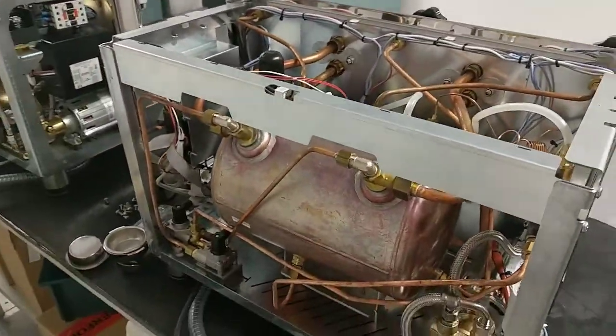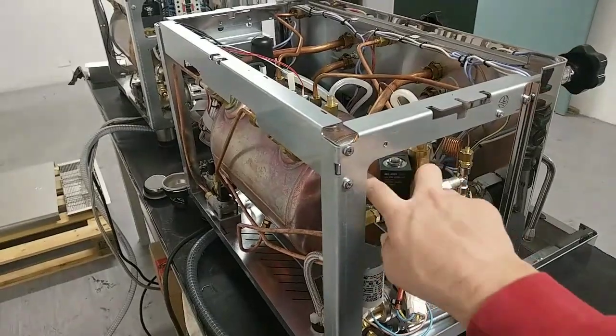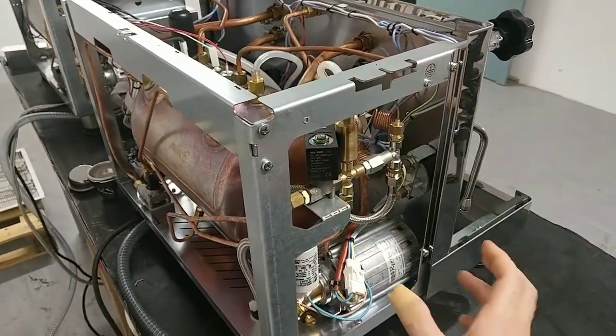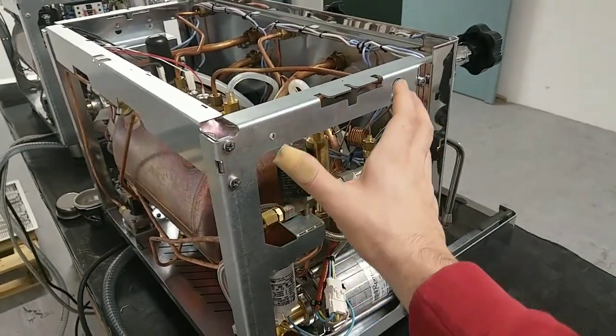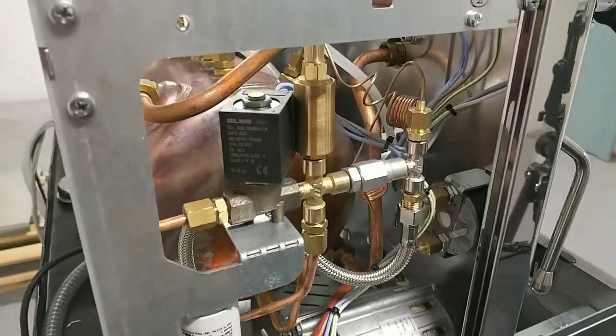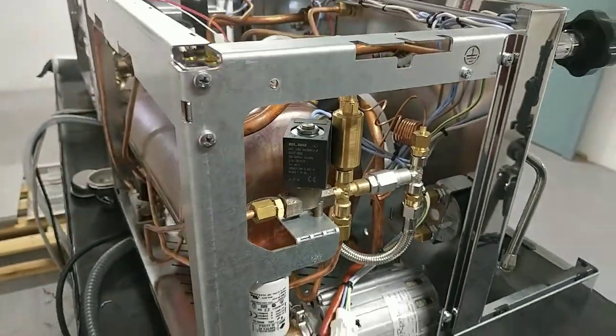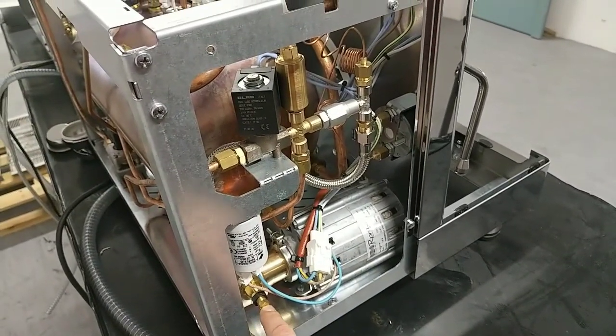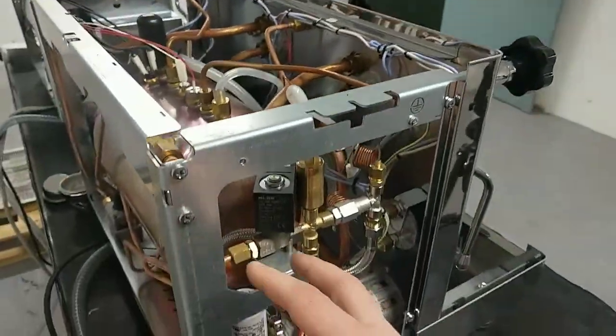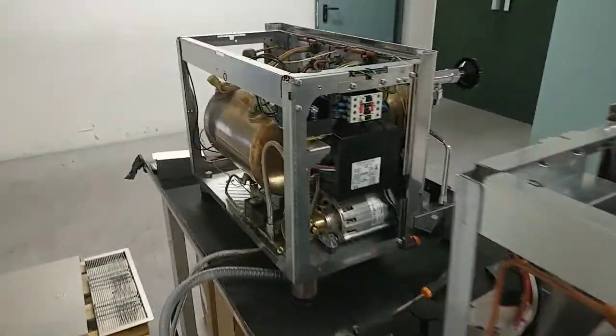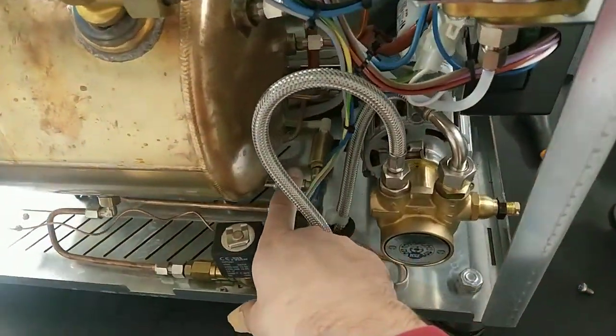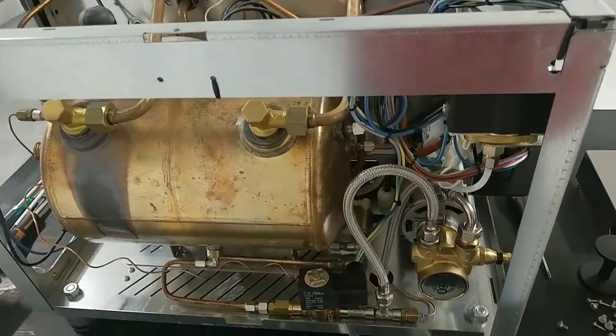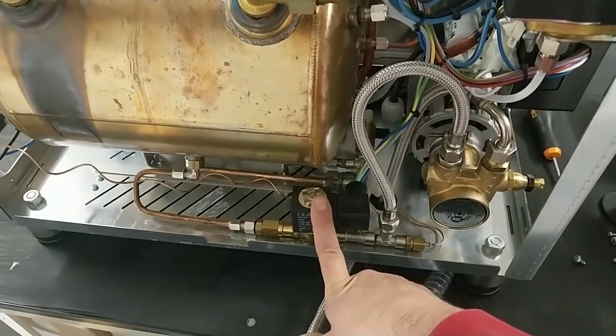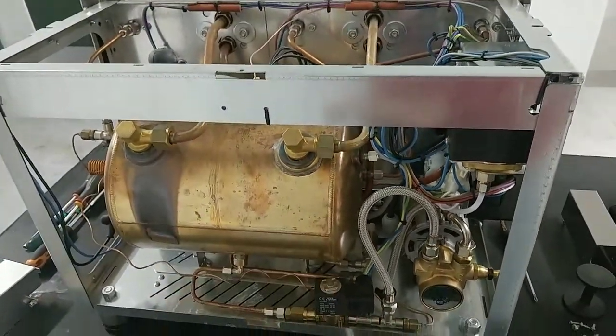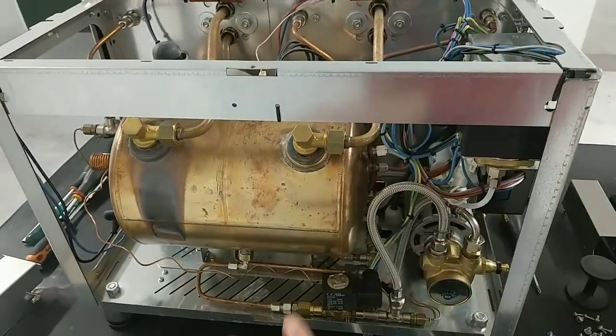For example, in the new version, if we have to do maintenance on the solenoid valve, it is easier. The water charge solenoid valve is easier because it's here. You have more access. Also, if you have to adjust the OPV valve, look, you have the pump. You can change the pump pressure, and you can change the OPV valve pressure. And you can remove only this panel, because you can access immediately everything you need. In the old one it is a little bit more complicated because the OPV valve is there, and to access it when the boiler is hot is very complicated. And also the water charge solenoid valve is here, and you have to remove all this panel of the machine.